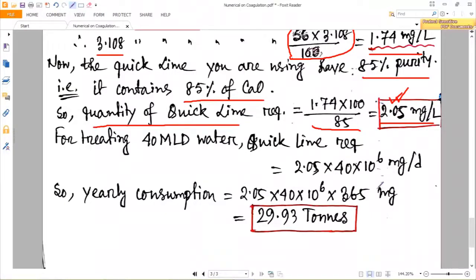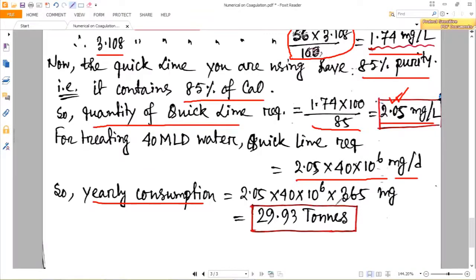The quick lime we are using has 85% purity, not 100% pure. Since CaO required is 1.74 mg per liter, and the quick lime has 85% purity of calcium oxide, the amount of quick lime required can be calculated as 1.74 divided by 0.85, giving a quick lime requirement of 2.05 mg per liter.